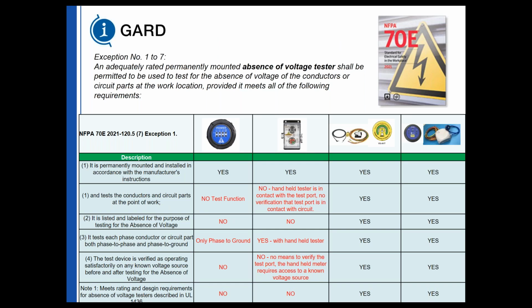So exception number 1 to 7: an adequately rated permanently mounted absence of voltage tester shall be permitted to be used to test the absence of voltage. So permanently mounted, yes, all these devices are permanently mounted. The test the conductors and circuit parts to the point of work. The Grace product does not comply with exception number 1 to 7. The portal does not comply because you have to use a separate test instrument. The Failsafe and the i-Gard i-AVT both comply. It is listed and labeled for the purpose of testing the absence of voltage. No to the Grace products, yes to the Failsafe, and yes to the i-Gard i-AVT.